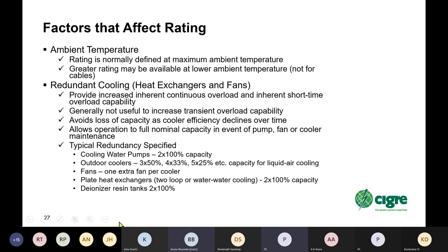That's really a function of the thermal time constant of the cooling of the electronic devices, and so that tends to limit the amount of transient overload you can get. If you have some redundant cooling in terms of extra radiator capacity, it avoids loss of capacity as cooler efficiency declines over time. There's always some cooler efficiency loss over time due to internal fouling or fouling in the radiators due to dust or pollen or other things. Also deterioration of the efficiency of the radiators. It allows operation to full nominal capacity, even in the event of a pump, fan, or cooler maintenance.